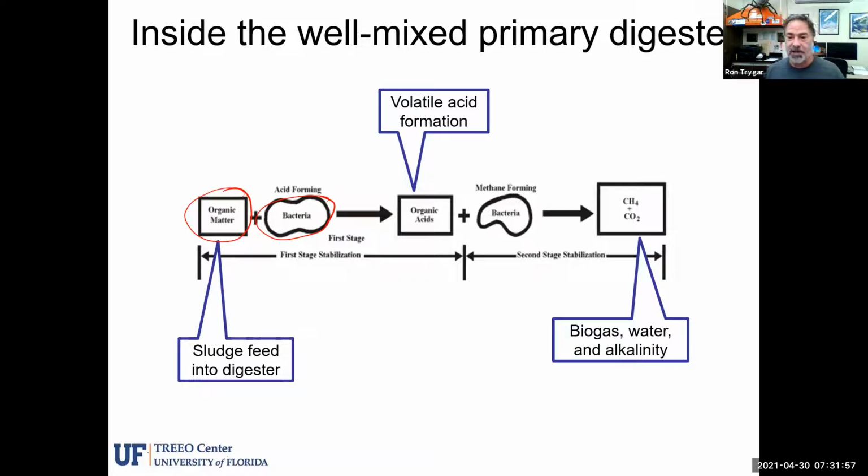So they're considered facultative anaerobes, and some of them are strict anaerobes. So they're operating without oxygen, without nitrate, nitrite. There may be some CO2 present, remember, or even sulfate, making some hydrogen sulfide gases along with this. But the main thing is that these bacteria are attacking the carbon coming into the digester.